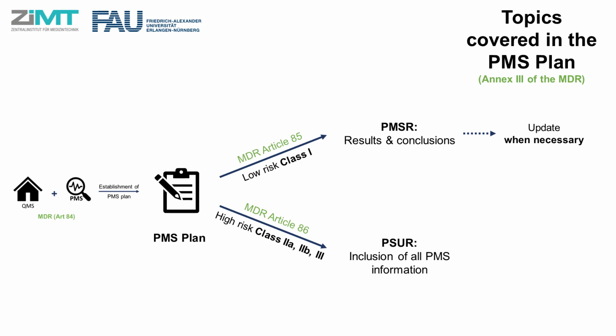Article 86 of the MDR describes the Periodic Safety Update Report as mandatory for high-risk devices, such as those in Class 2A, 2B, and 3. The manufacturer shall include in this report all the information present in the PMS and add a summary of the market where the device is integrated in Europe, as well as information about the post-market and vigilance reports. The manufacturer shall then regularly update and send the report to the authorities to be examined.